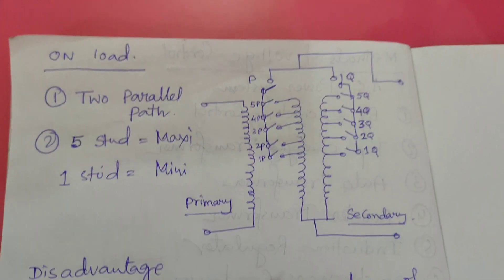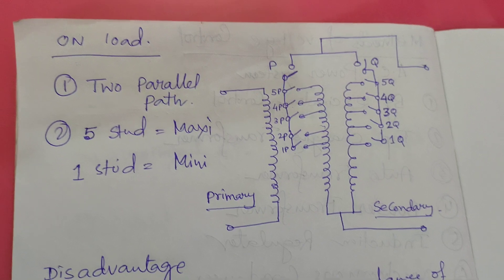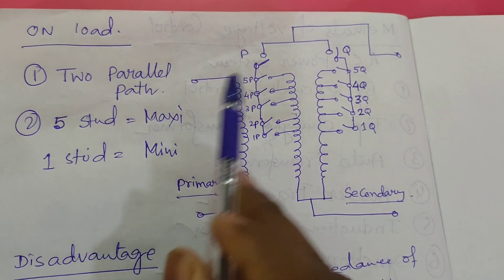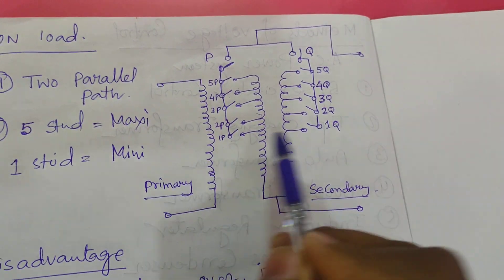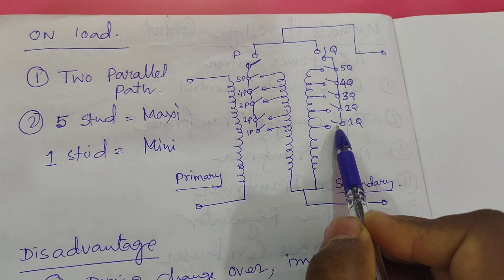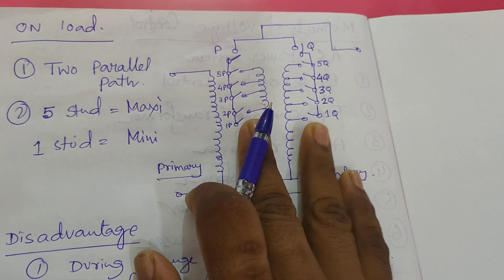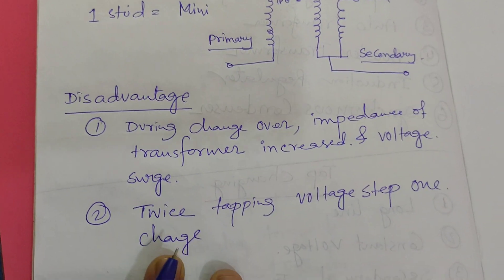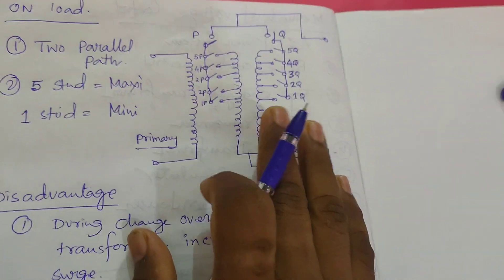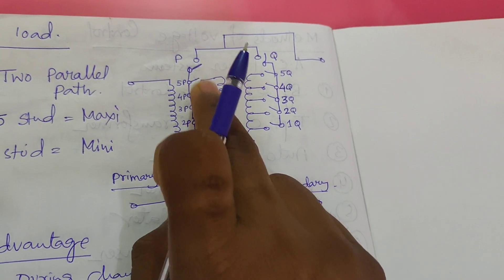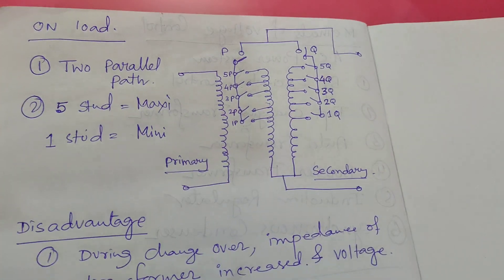To avoid tripping due to this voltage dip or voltage surge, you must adjust the relay settings accordingly. Tap position 5P and 5Q provides the maximum voltage, while 1P and 1Q provides the minimum voltage — change the tapping as per your requirement. A key disadvantage of onload tap changing is that changing one tap requires two steps: both the P and Q sides must each be switched, making it a critical two-step procedure.